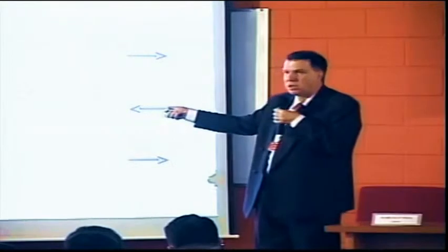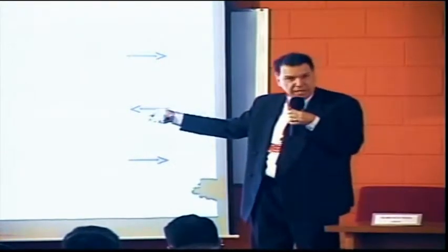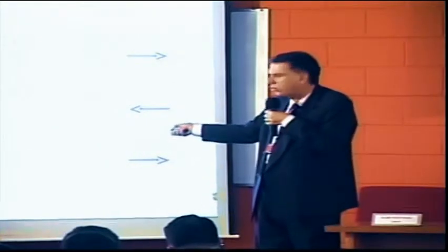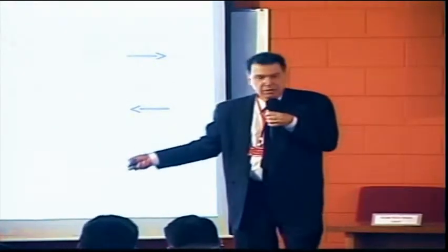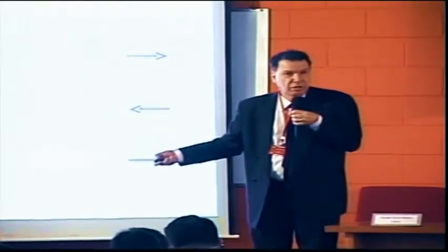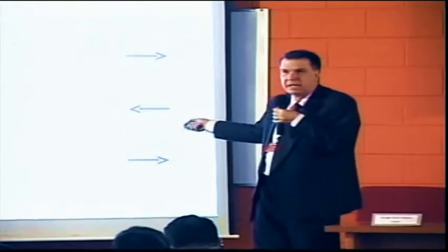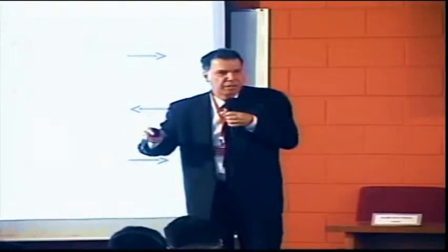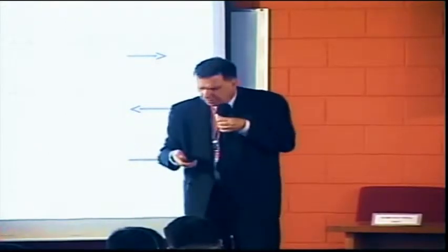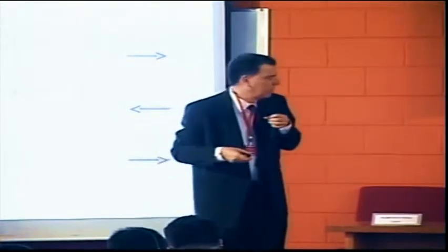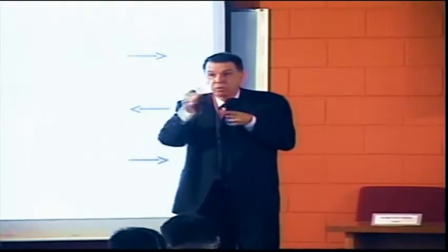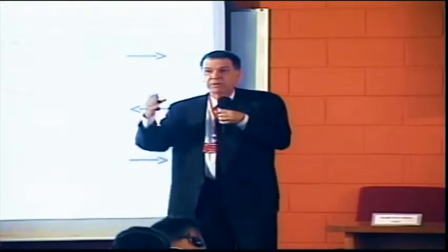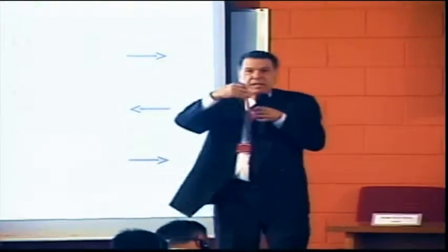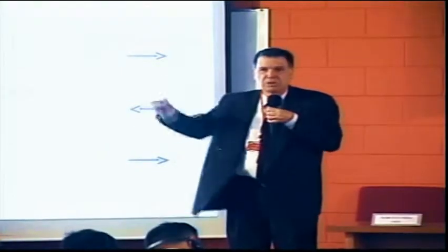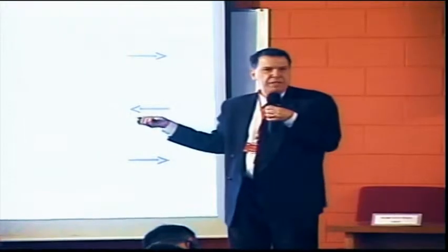The idea is for this circuit breaker, in blue, the one in Serra da Mesa, to be maneuvered, and we would reach the voltage in Bom Jesus da Lapa. To prepare this link of 2,600 kilometers, we would remove all the series compensation, bypass the shunt compensation, and remove the surge arresters. This was a point discussed, because removing all the surge arresters and preparing the link would take a long time, since we have surge arresters on each phase, requiring a large team to remove them simultaneously from all the substations. We'll see ahead that this was not necessary.